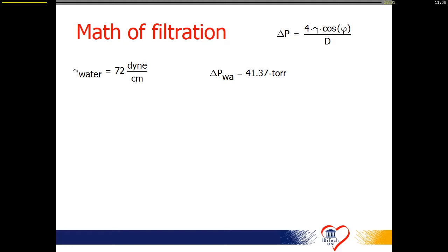That means these are the data most people take with them home, because this is what the companies are providing us. This is what the majority of studies are providing us. But if you change it just to blood, as you can see immediately, these filters become less performant. And that's one of the reasons why you see that in the initiation of bypass, there is always a small increase in the number of GME which are actually passing this filter.